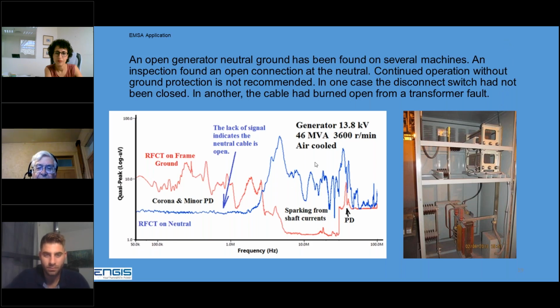So we get this pattern because there was some arcing of shaft currents at the grounding brush on the shaft. But this says it's open. So we move the probe to the ground of the generator, the safety ground, and we got the red curve. That was the one we used for data analysis. And when they did the inspection, they found that the cable was opened up here. All of these connections in the grounding cage were good.